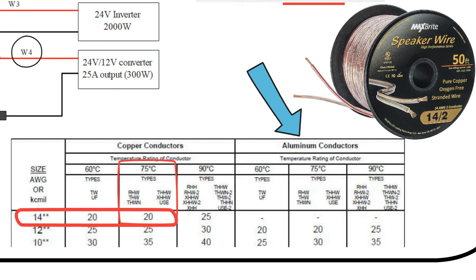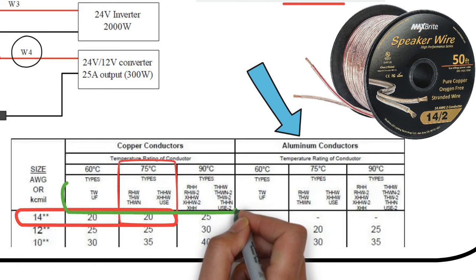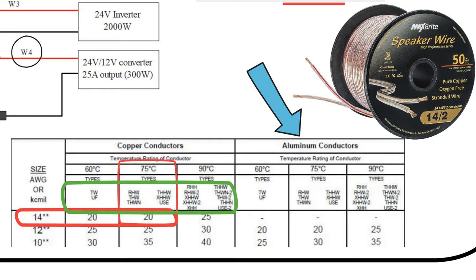If you don't find the wire's temperature rating, you can look at the type of wire illustrated on the sales page or on the wire itself. In the NEC ampacity table, you can see different wire types that fall within the 60, 75 and 90 degrees Celsius specifications. Here is a table if you want to compare American wire gauge to millimeter squared.